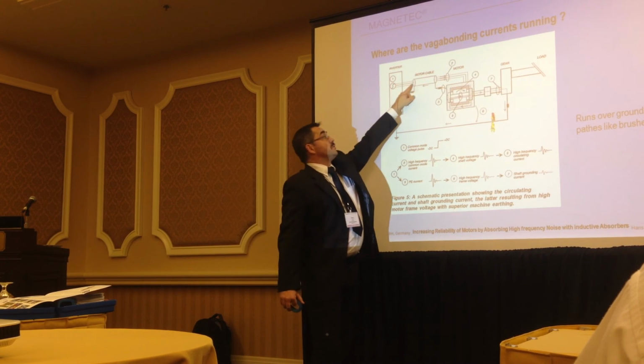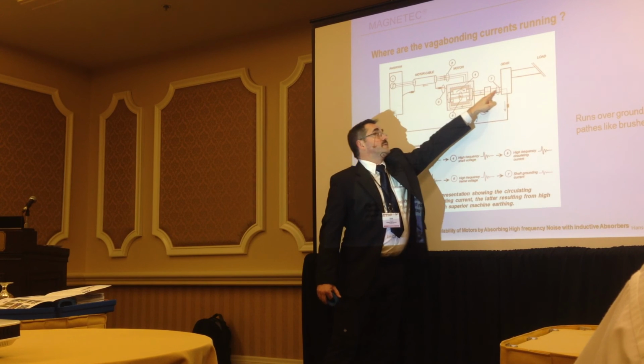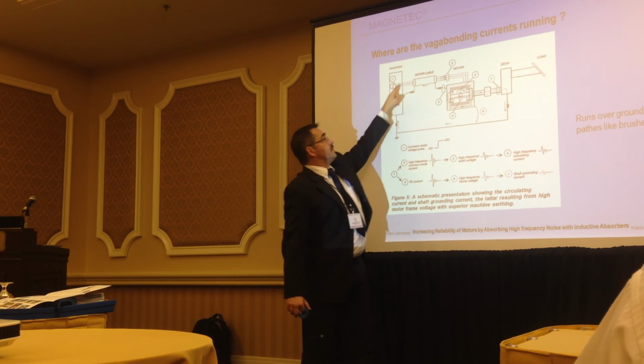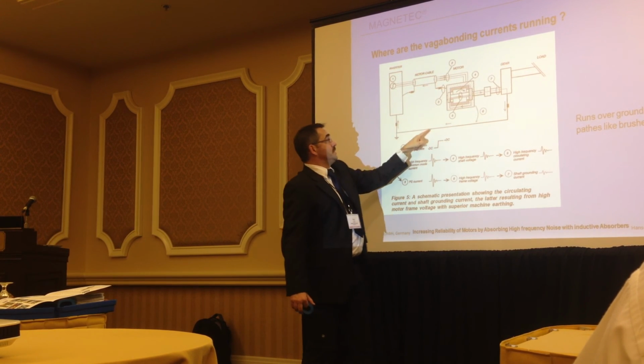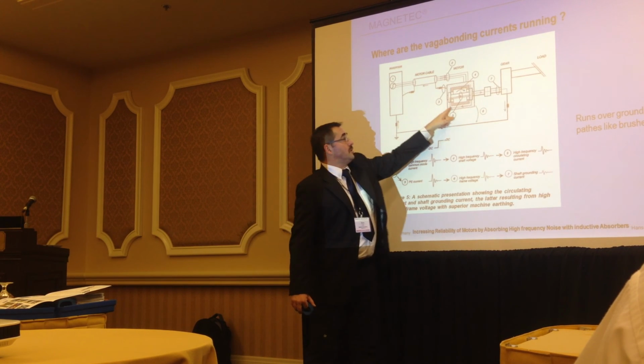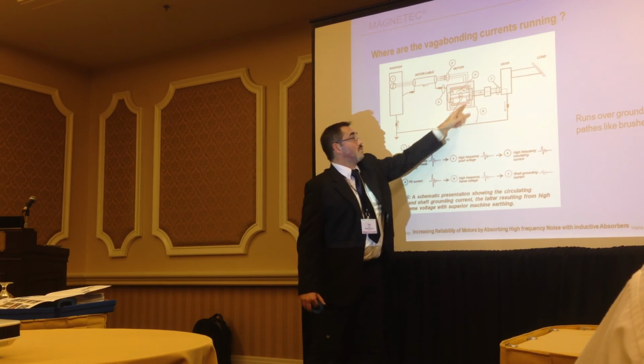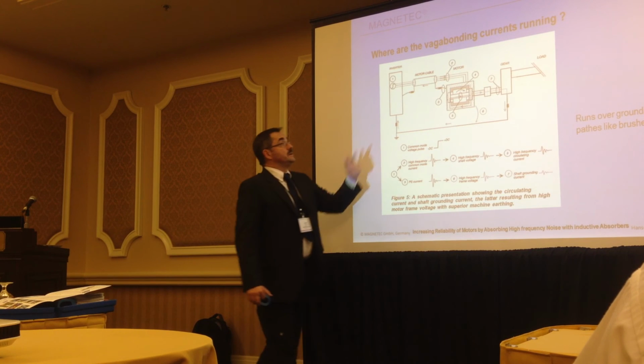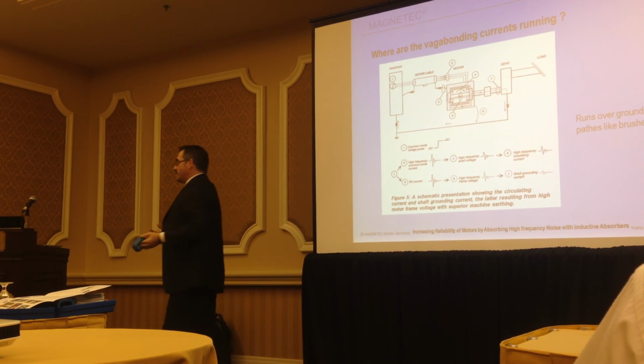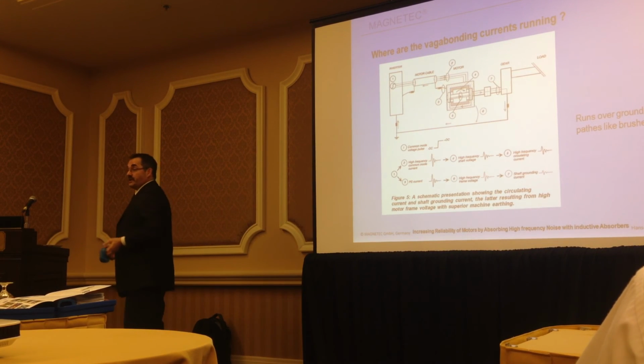This common mode current can come up over the gearbox, or it can come up directly over the shield, parasitic capacity, over the bearing, over the case of the motor, or some other paths. That's not so easy, and that's the reason why these currents are named vagabonding currents.